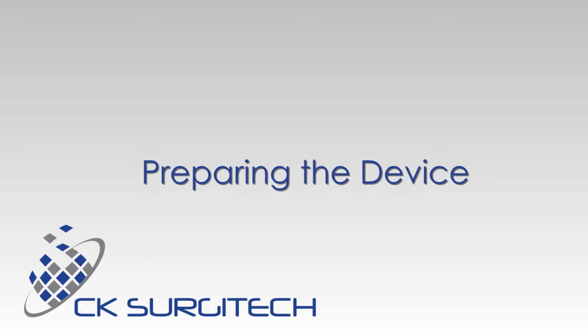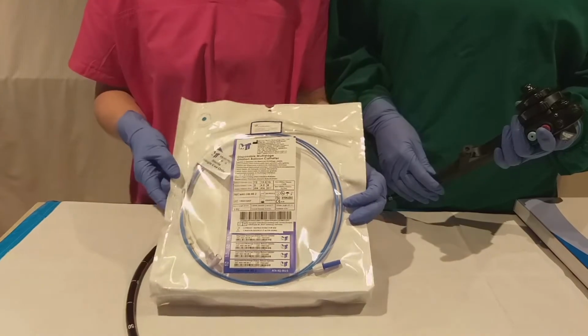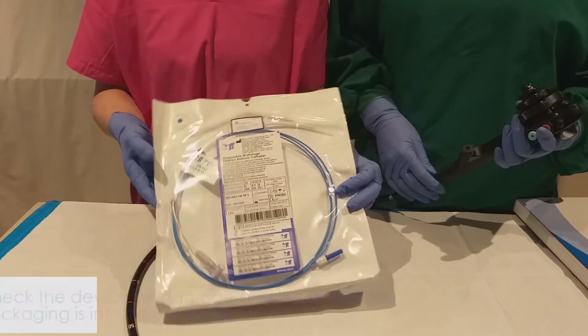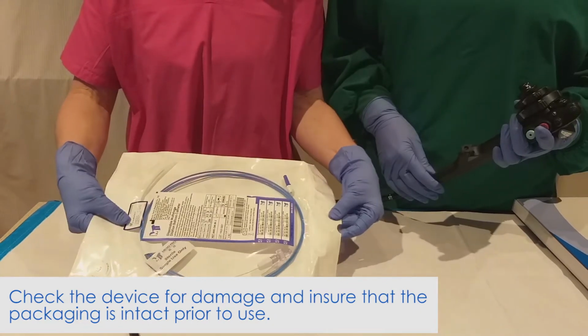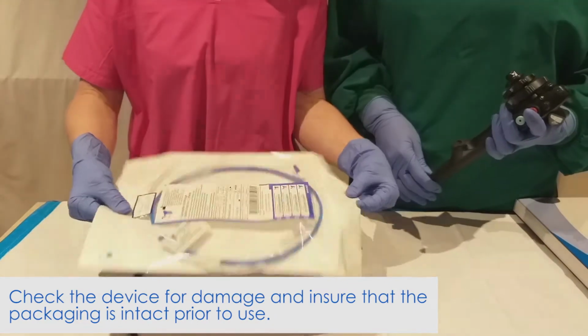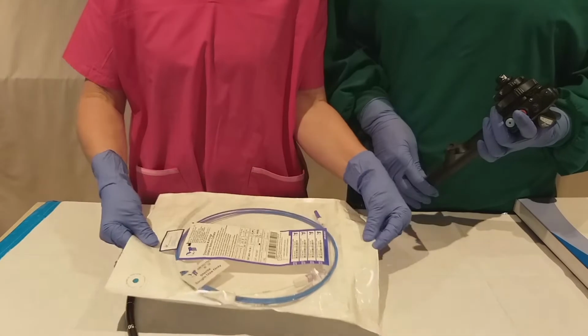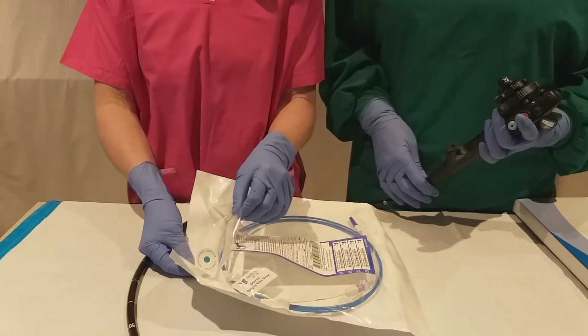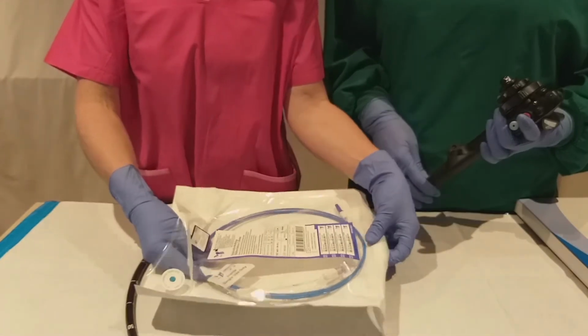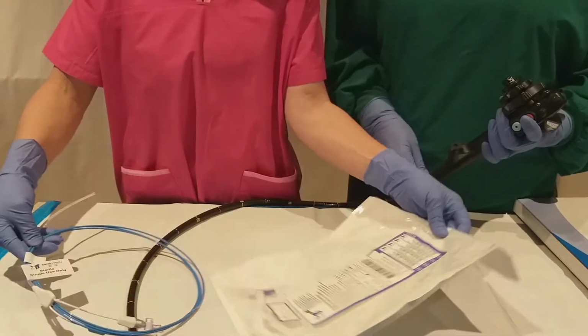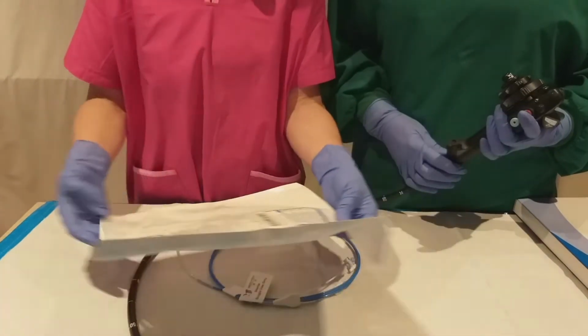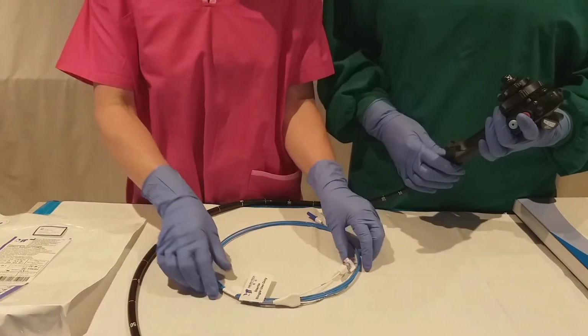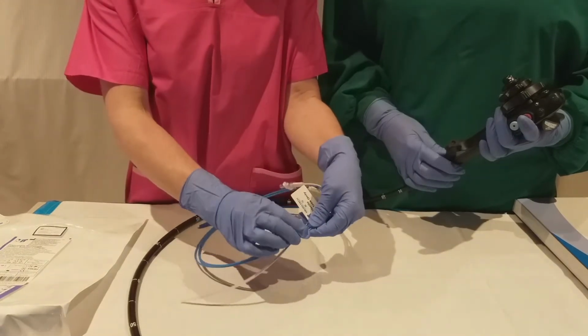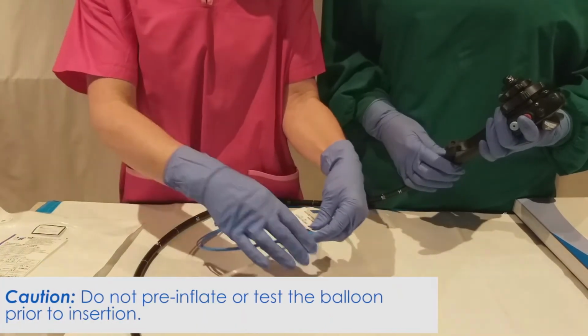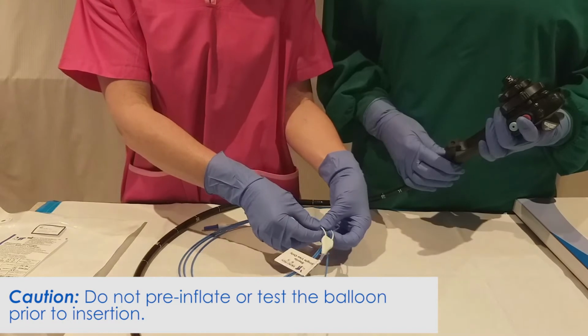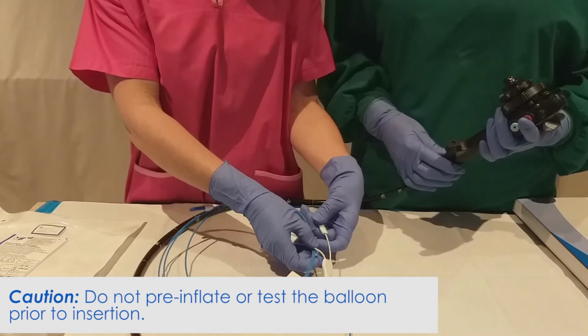Preparing the device. Each balloon comes packaged in a plastic peel pouch. It is important to check the device for damage and ensure the packaging is intact prior to its use. Open the pouch and carefully remove the device from the packaging. Remove the paper tag to uncoil. Caution: do not pre-inflate or test the balloon prior to insertion.